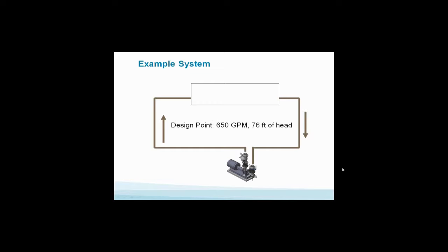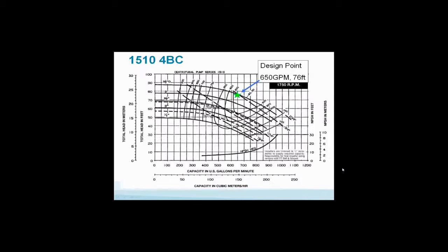Design flow by the engineer is 650 GPM at 76 feet of head. But you know what? Pumps are stupid. They don't know that your design head is 76 feet, and they just might run at some other number. Let's just see what happens in this case. Let's turn the pump on. Here's the pump, a 1510 4BC pump.